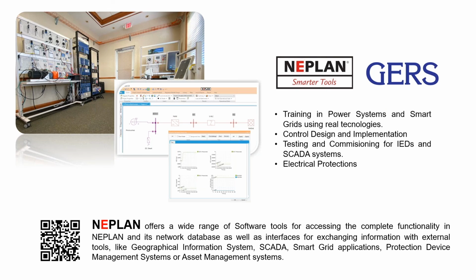So we are the NEPLAN representative in the Americas, and our services using NEPLAN include training in protection schemes and smart grids using real technologies. We have here a picture of our laboratory that has a real microgrid implementation using different IEDs. And also we have integrated that into our SCADA system, and the SCADA system was automated using the NEPLAN web services. We can design, control, and test protection schemes. We can test any IED or SCADA system, and for sure we can implement the proper setting criteria for the protections.